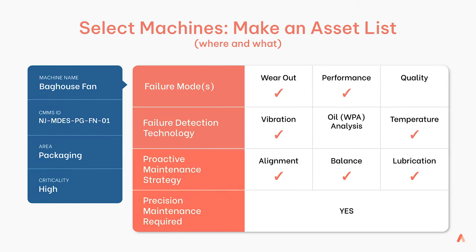The next step, once we've effectively defined what our important pieces of machinery are, is to define their failure modes and the most effective failure detection technology. Different machines are going to fail at different rates depending on what they're doing and their design — it could be hours, days, weeks, or months. Typically you're going to want to sample the machines at four to six times the rate of failure. We're not going to talk about protection systems today. What we are going to talk about is how we employ vibration. You can see from the chart we've looked at this bag house fan and it's got different failure modes — it wears out, it can have a performance failure, and there's always a quality consideration. The technology we're talking about today is vibration.